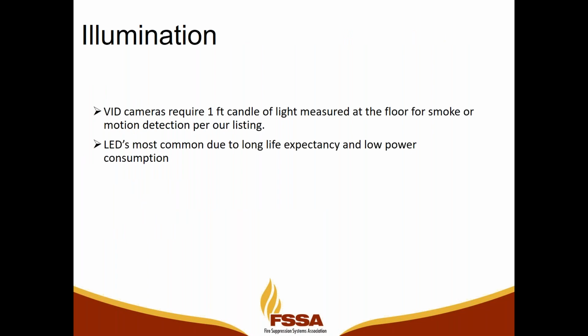Video analytics require 1 foot candle of light measured at the floor according to the code or the standard for smoke or motion. Flame and reflected flame create their own light, so they can be used in dark conditions. LEDs are applied commonly because they have a low power consumption and they can light up the area sufficiently for detection.